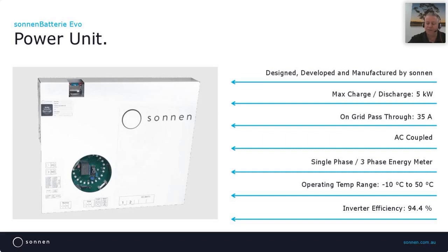The sonnenBatterie Evo is a single phase model. However, like previous Sonnen models, we provide a 3-phase energy meter that can be programmed using an LCD screen to read all 3 phases of a site. The sonnenBatterie will react based on the information received across all phases, and net metering will net the readings from the 3 phases for the customer's billing.